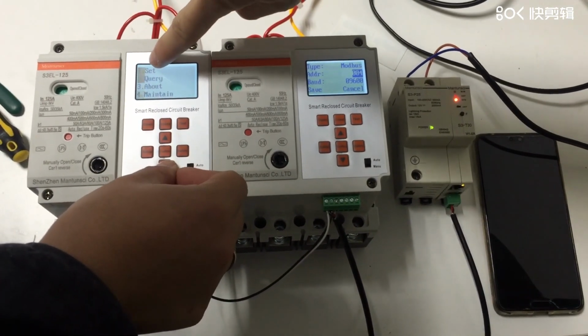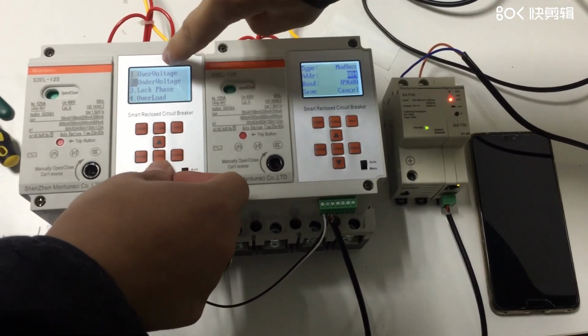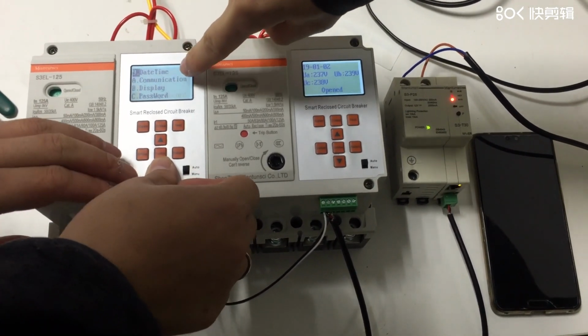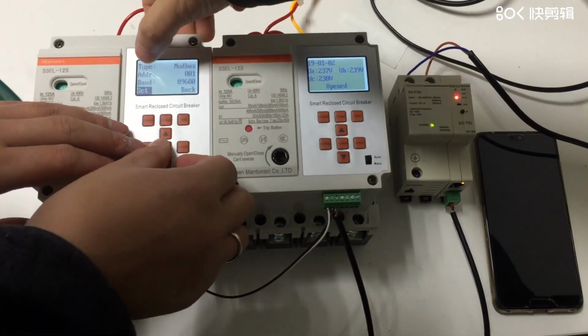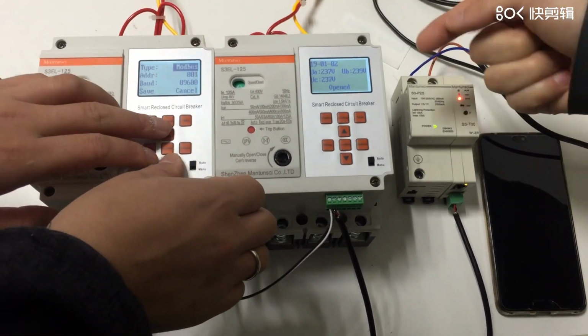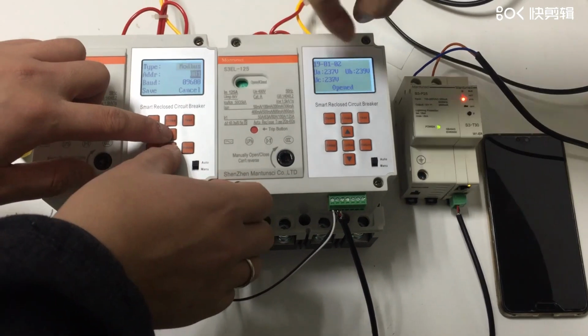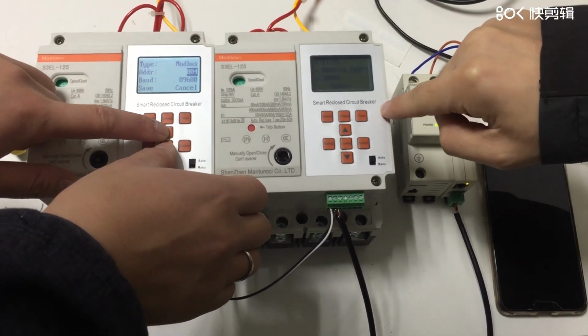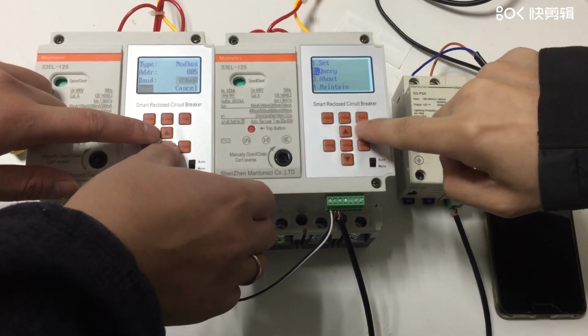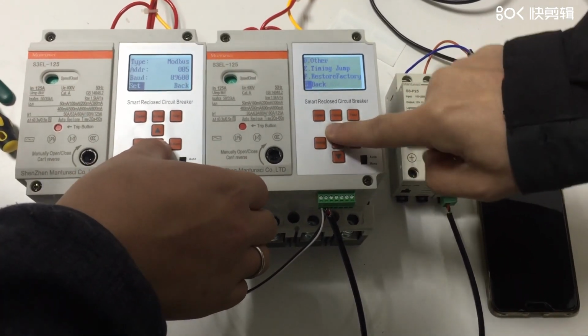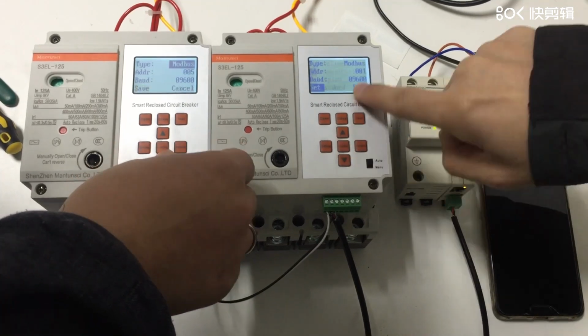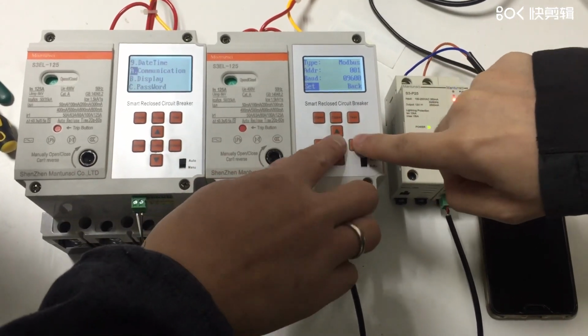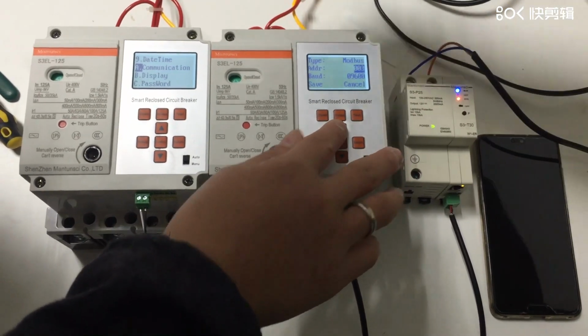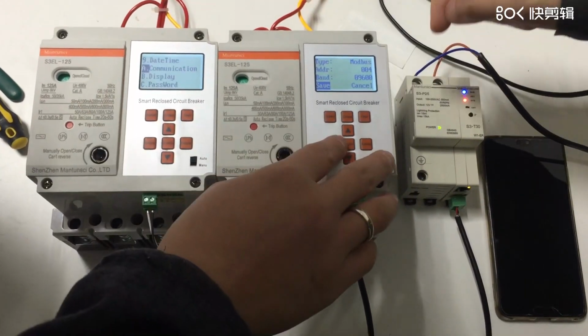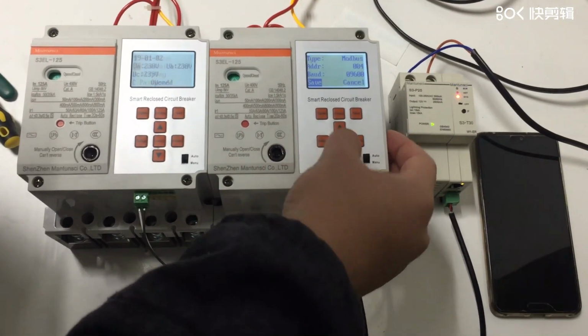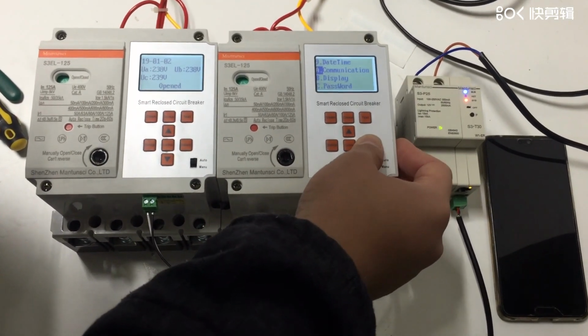Press set, and then press set, also set, and then go to A, communication. Okay, communication, and we are going to set up the address as 3 and 4. They must be different. Like this one, we can set up the address to 4. So this one is a 3. And they must be different, fine. Otherwise it will get conflict and they will not know.